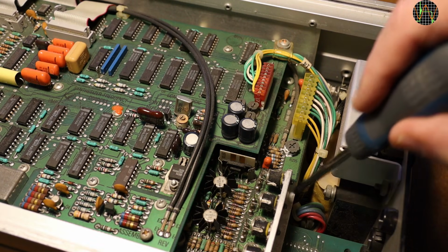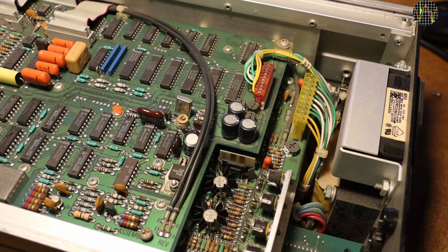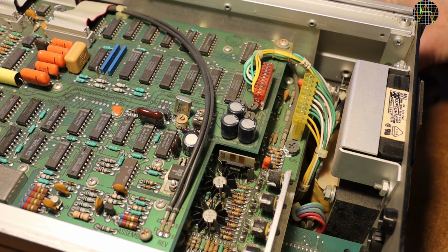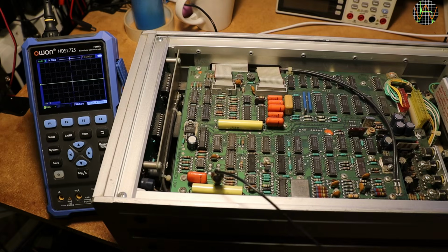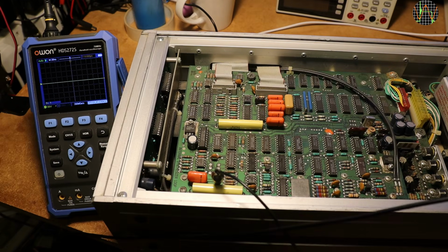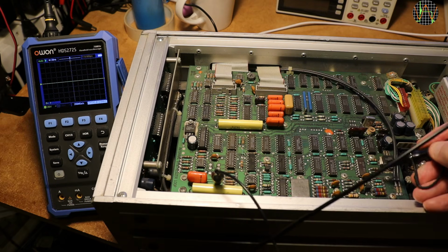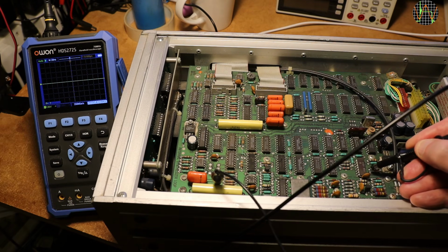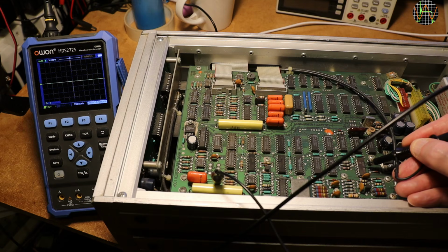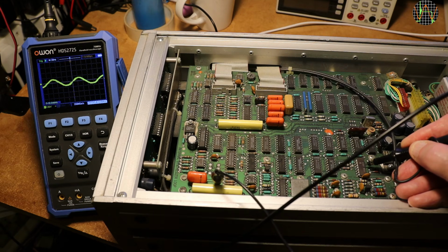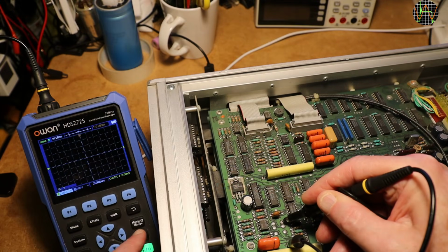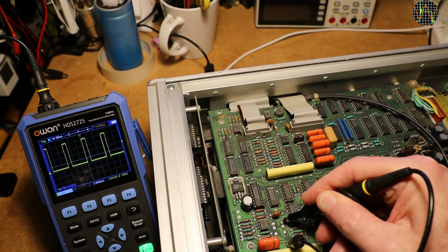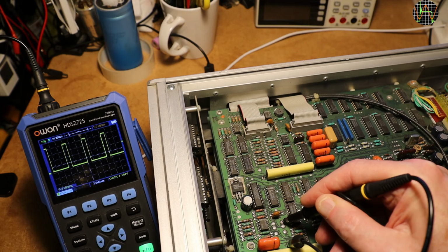Looking down at the rear, you can just see the underside of a third board, but that is the power supply processor board we saw earlier. It turns out nearly all the chips mentioned in the service manual troubleshooting guide are on the topmost board, which is very convenient. I tested around the components mentioned, but did not see anything amiss. Here is, for example, the 3.2 kHz reference signal that plays an important role, and there's nothing wrong here.